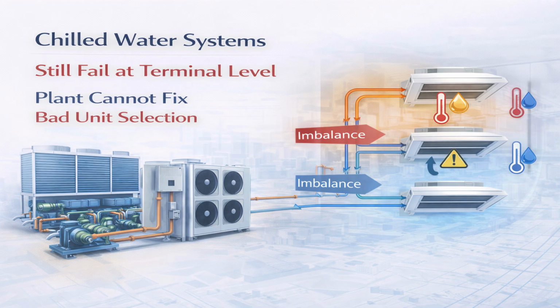Chilled water systems often give a sense of comfort and safety because of the central plant configuration. There is redundancy at the chiller level, there is flexibility in distribution, and it's easy to assume that the plant will compensate for any issues downstream. However, in practice, terminal unit selection still plays a critical role in overall system performance. If the chilled water temperature difference is not aligned with the design intent, or if the coils are oversized, or if the control valves are poorly matched, heat transfer at the terminal level becomes inefficient and unstable.